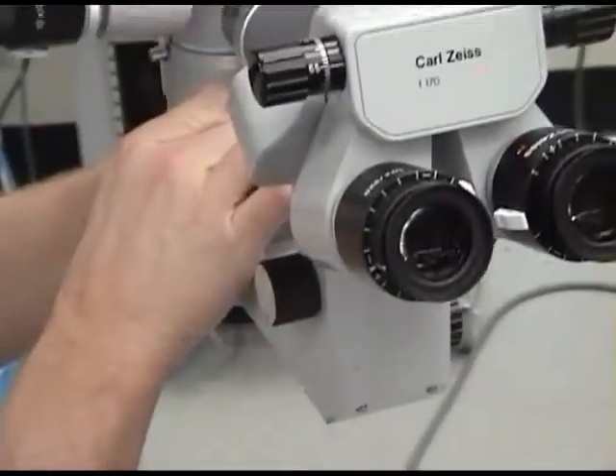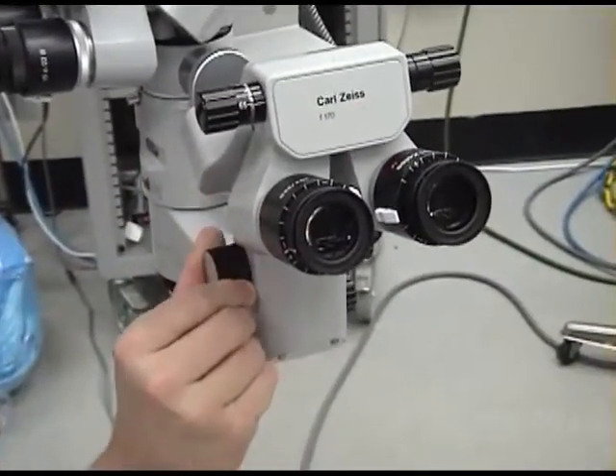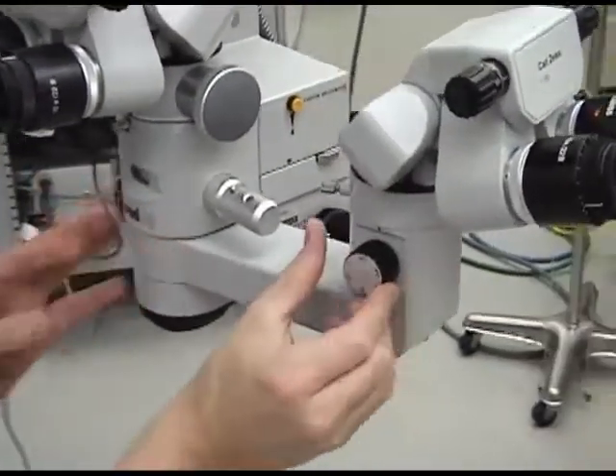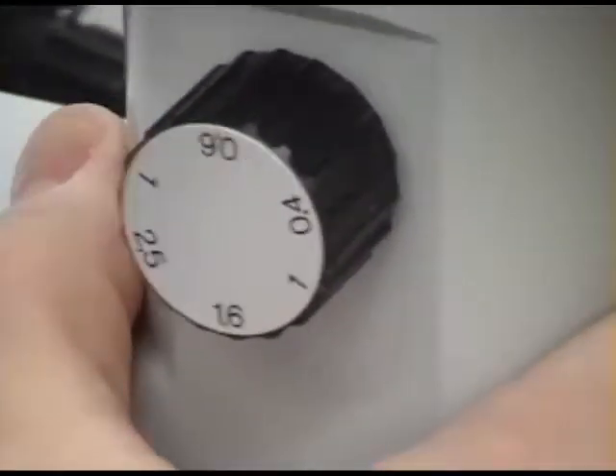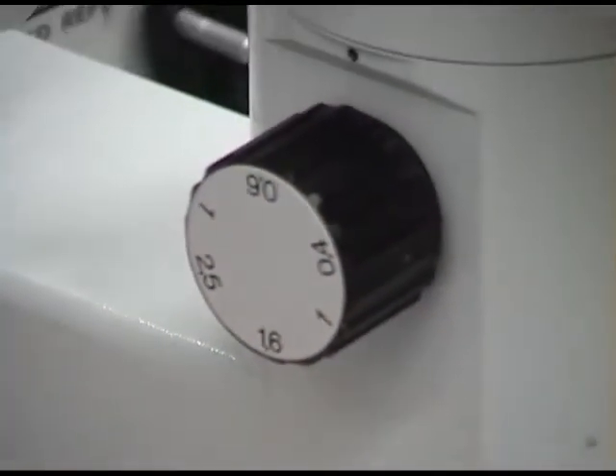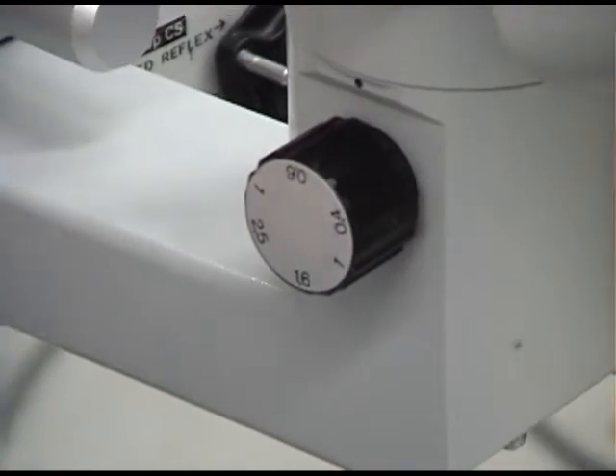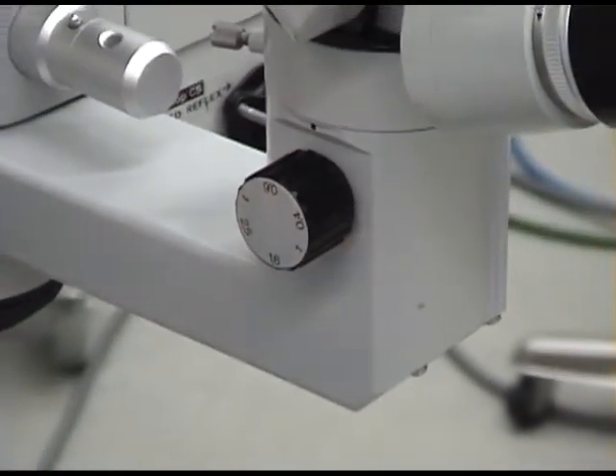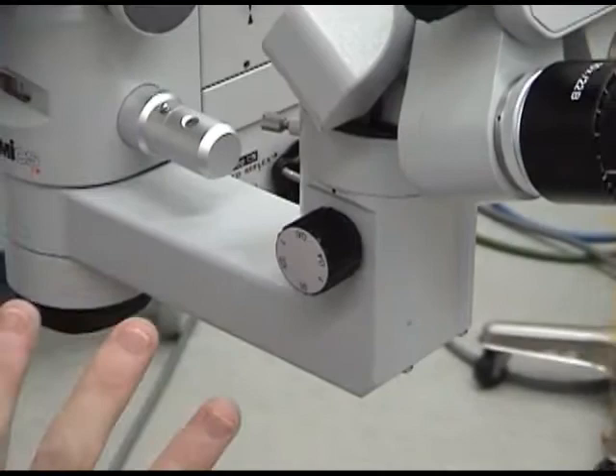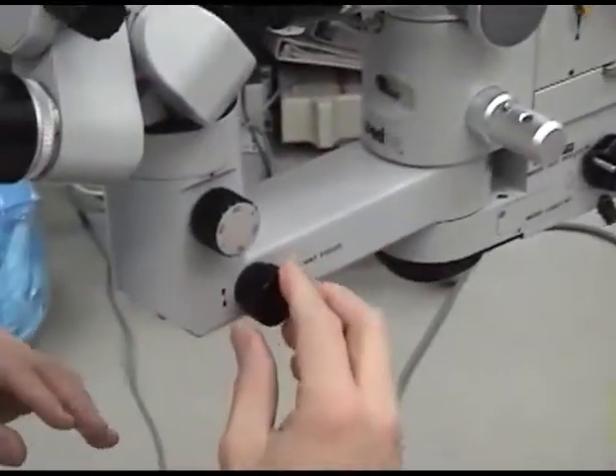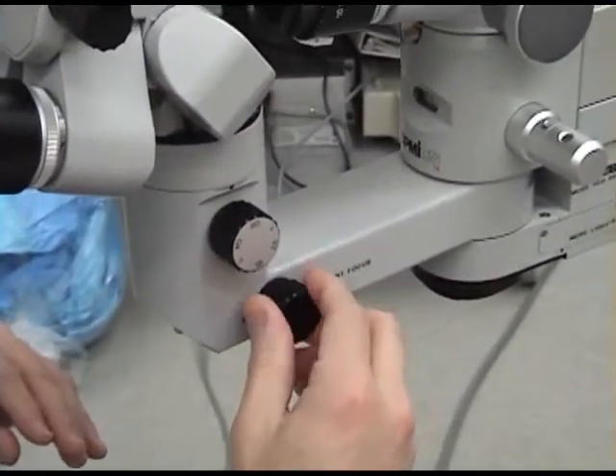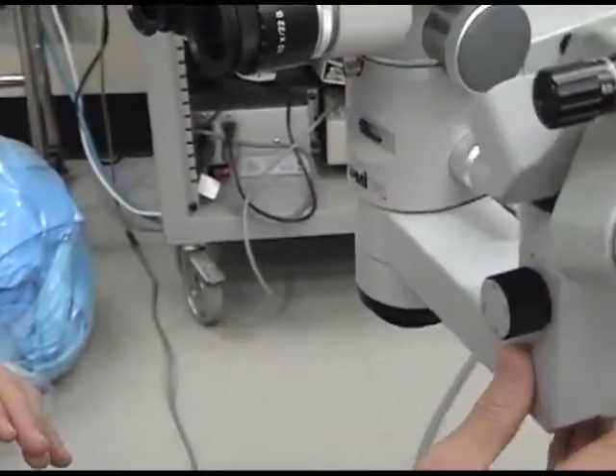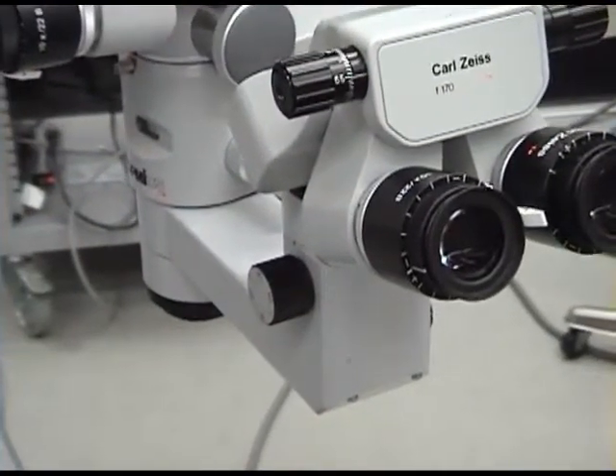Now the assistant has a separate mag switch. Here you can see fixed at 0.4, fixed at 0.6, fixed at 1. So the assistant has a different zoom than you have. Now as this moves up and down, the assistant will have a similar focus to you. So usually as the surgeon moves down or moves up his or her focus, the assistant's in sync. But there is a separate focus knob here that helps the assistant if there's some difference in accommodation or something.